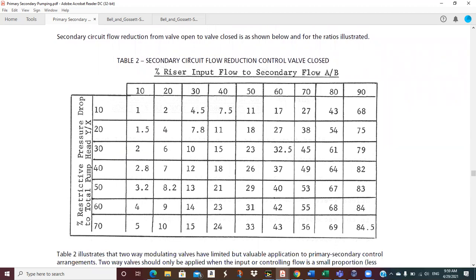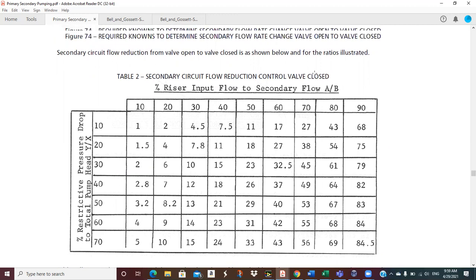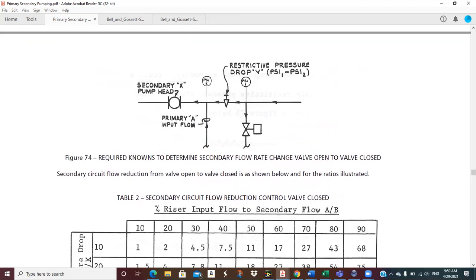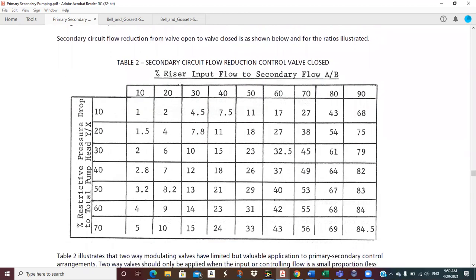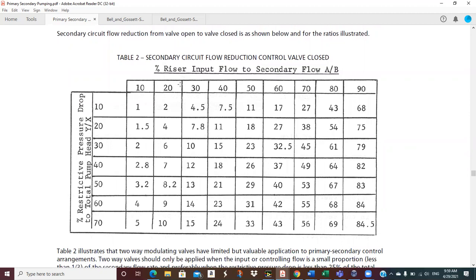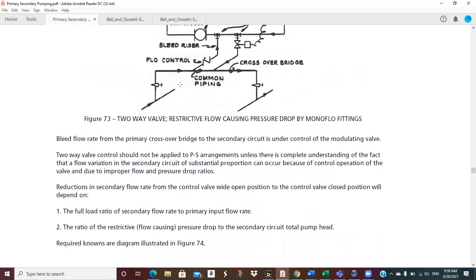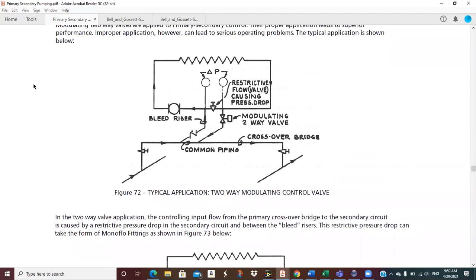So across the top, I've got the percent riser input flow to secondary. So that's A over B. A is what's coming up from the crossover, and B is what's being circulated up here. We just take that, and he's done it in a percent. If we've got really hot water, then that crossover flow is small, and we do that mixing thing. So if this is 250-degree water, then I bring it up here. This might be 5 GPM, and this might be 20 GPM that I'm circulating. So 5 divided by 20 would be 25%. And then you would look in that table at the 25%.